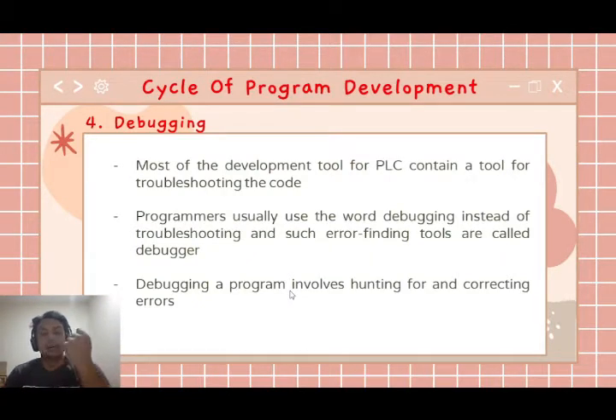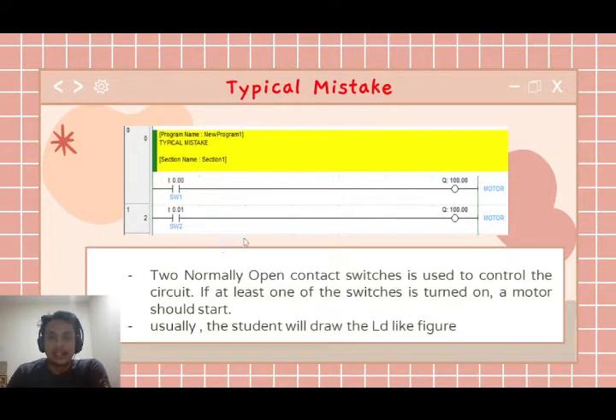Okay, we go to debugging. Most development tools for PLC contain a tool for troubleshooting the code. Programmers usually use the word debugging instead of troubleshooting, and error finding tools are called debuggers. Debugging a program involves hunting for and correcting errors. Okay, we can see a typical mistake in this program. Two normally open contact switches are used to control the motor. If at least one of the switches is turned on, the motor should start.